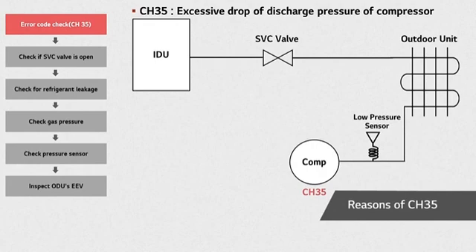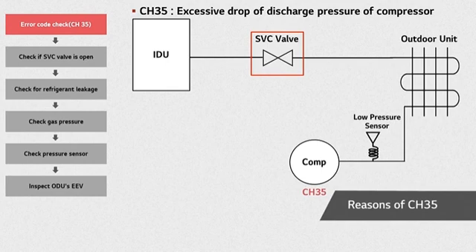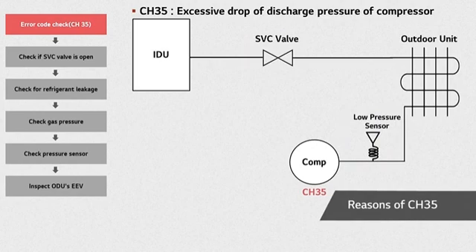CH3-5 is an error related to a drop of the compressor's discharge low pressure. Low pressure drop will cause the compressor to remain in off state. Common causes of this error include service valve blockage, lack of refrigerant, defects in the low pressure sensor, a malfunction of the IDUs or ODUs EEVs, etc.